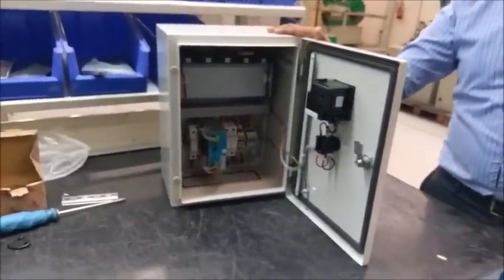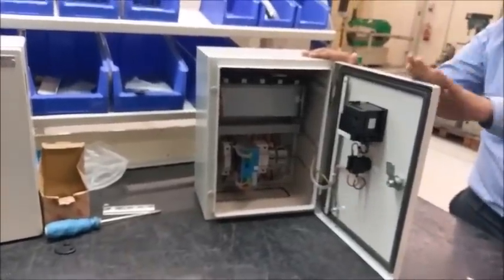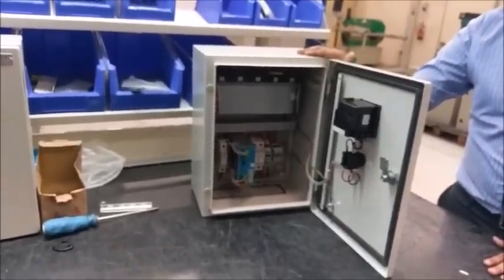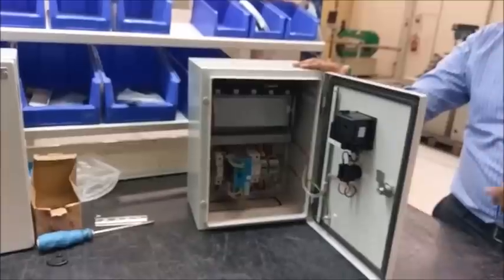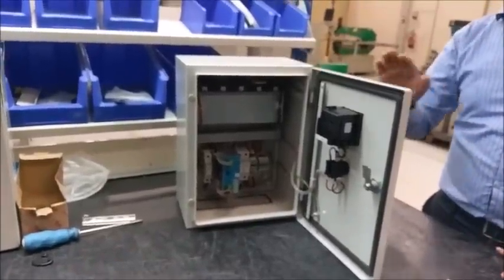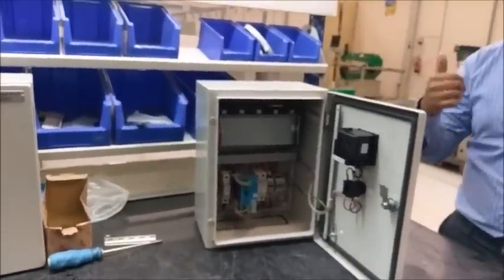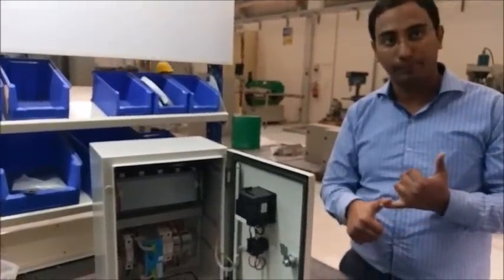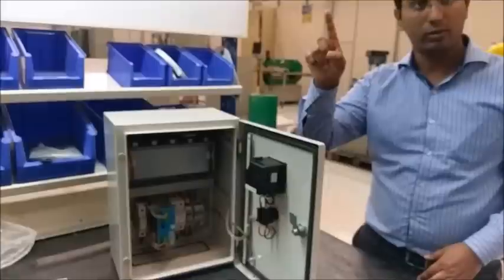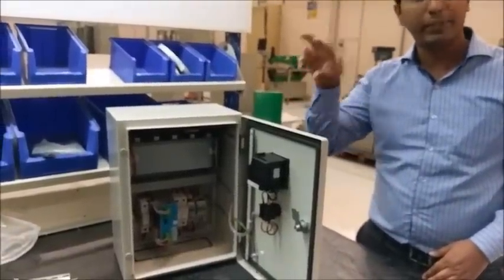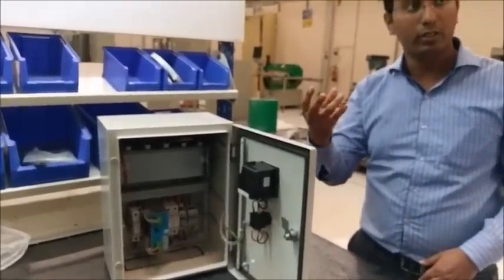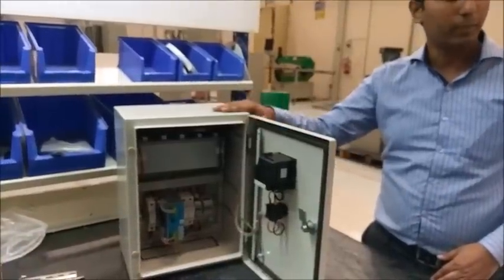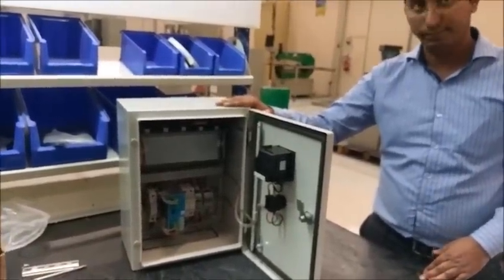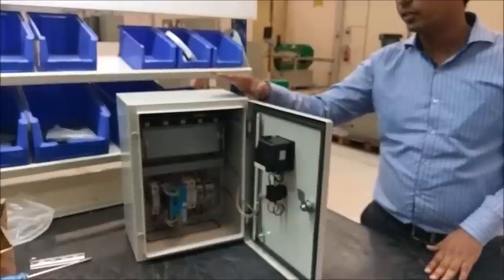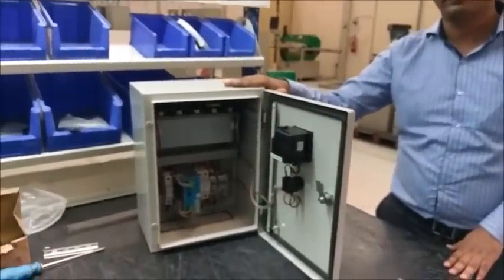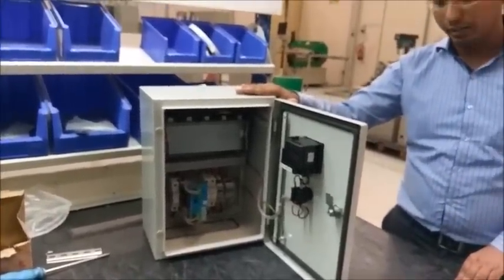For now, this is for the Karama LV panel. For the main breaker, there is a short circuit happened. No, this is not for short circuit. If there is a REF fault, REF will close the contact, but that contact will go to the tripping coil. To energize that tripping coil, supply is required. For the ACB, air circuit breaker tripping coil, that supply is required. This is that supply, named battery box.